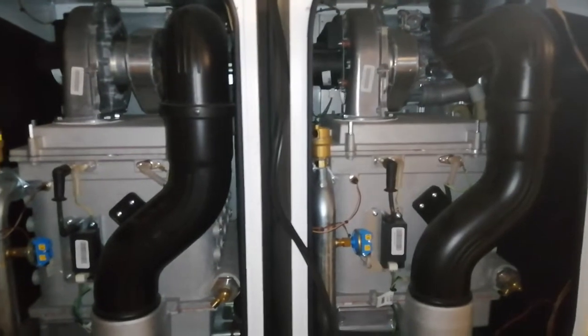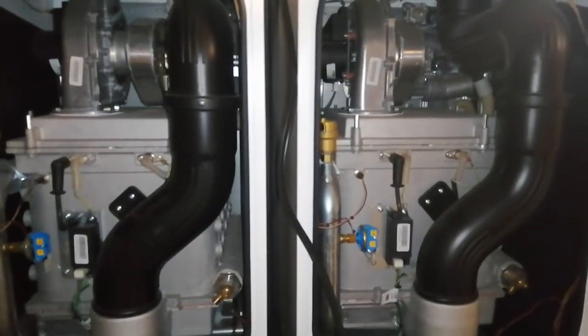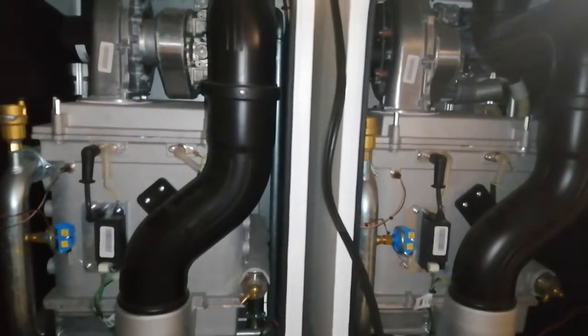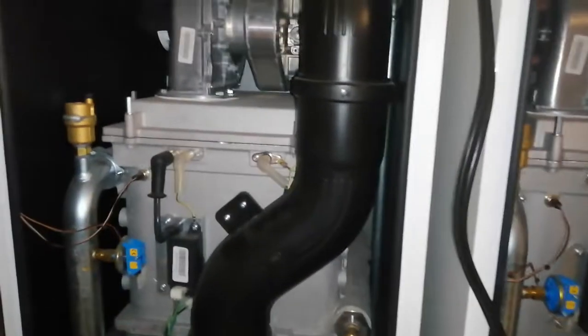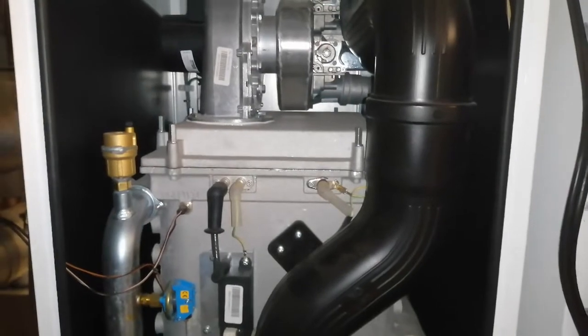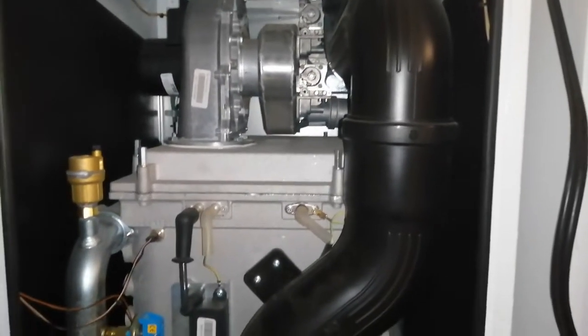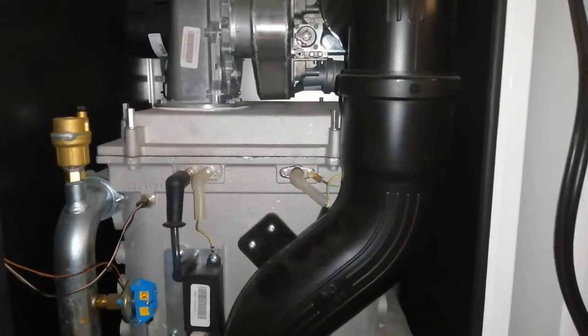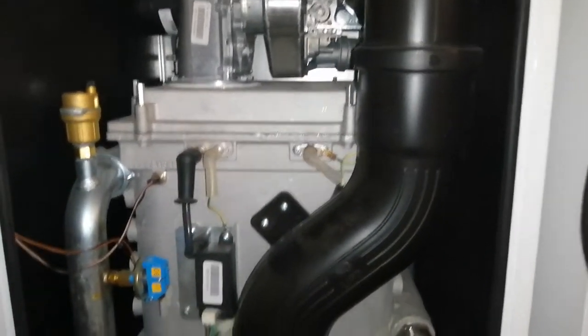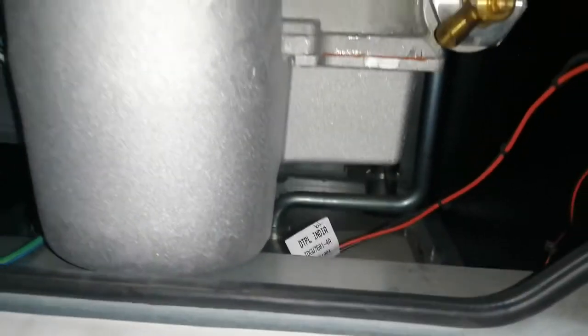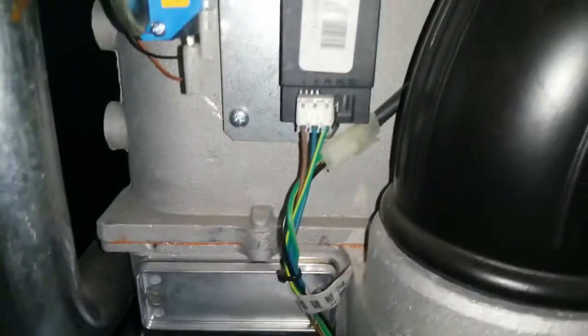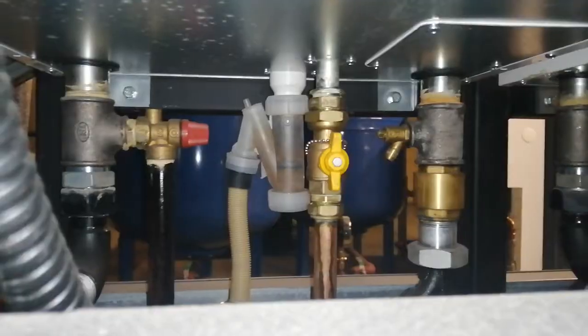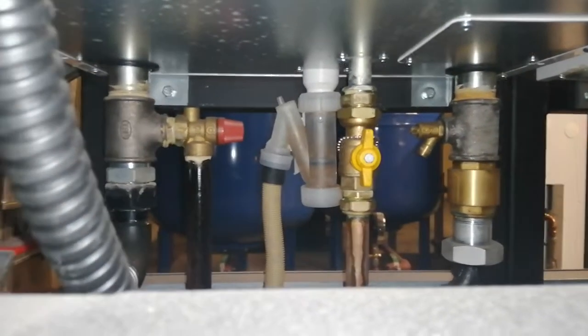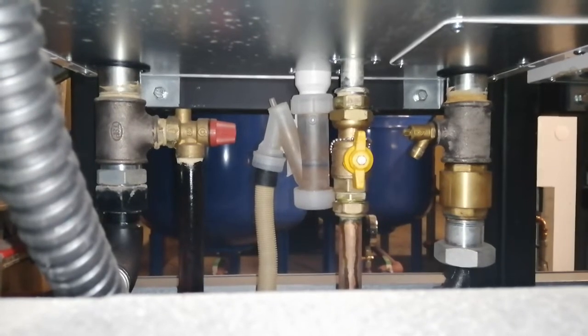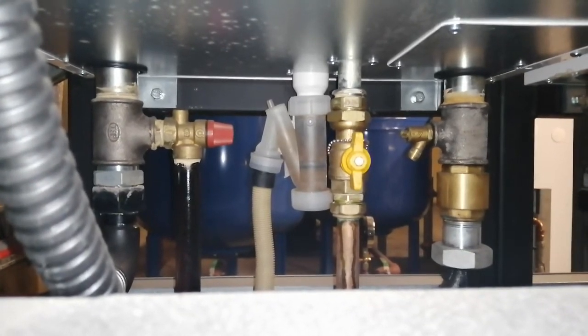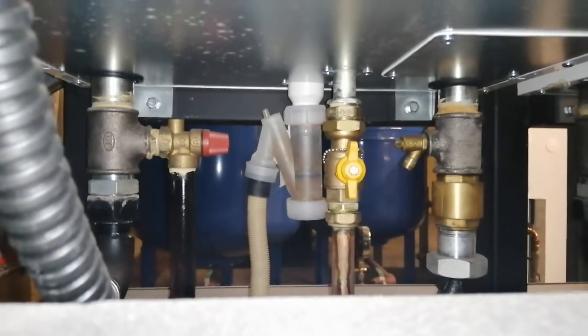Just carrying out servicing on 5 units here, Evo Max 150s. Do remember when carrying out minor servicing that you should refer to the manufacturer's instructions, ensure that you're Gas Safe registered as well. On this unit, having a look inside, making sure there's no signs of leaking and so on. And then also checking the condensate traps that they are clean. You can give them a flush through if they are dirty. These look like they need a good flush through.